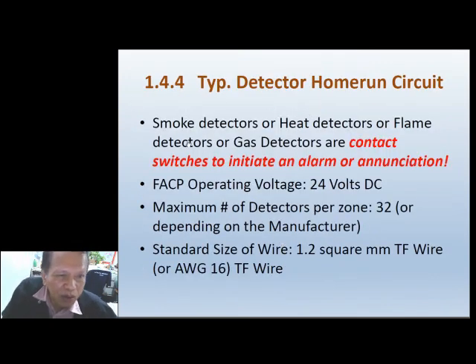But how about the wiring for the smoke detectors and heat detectors? Well, the wiring there uses small wires, usually TF wire at 1.2 square mm, or AWG 16 in American wire gauge. The operating voltage is usually 24 volts DC, and the maximum number of detectors depends on the product and the manufacturer.